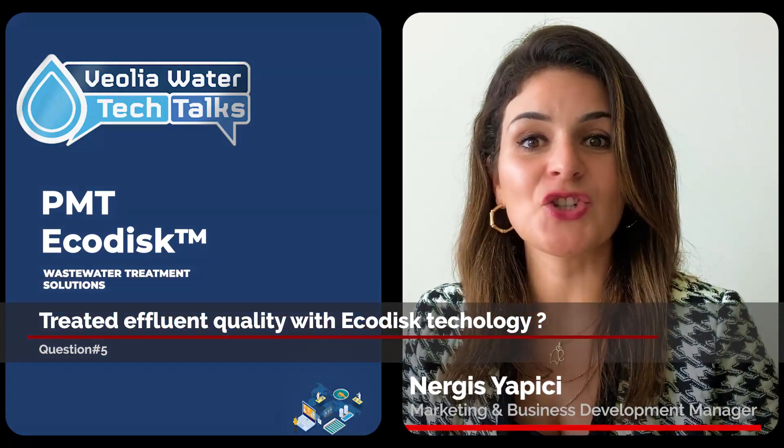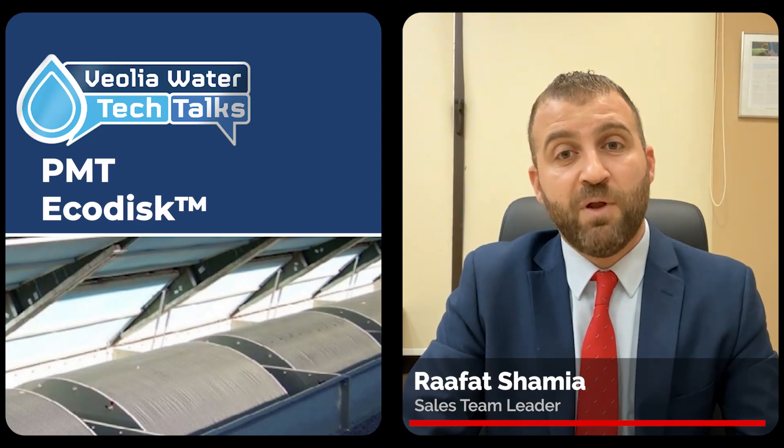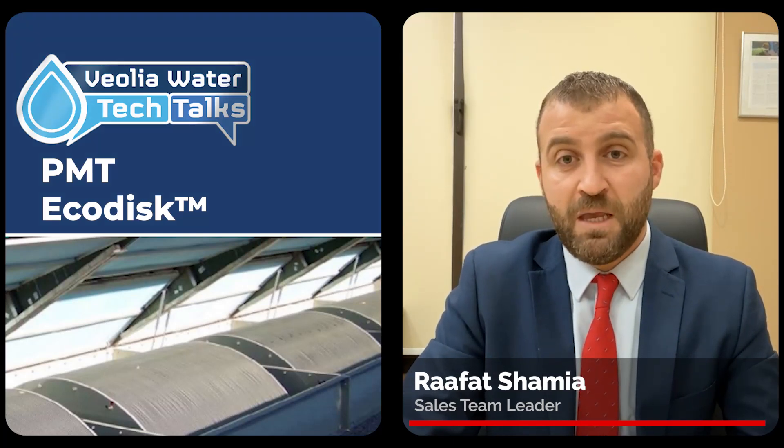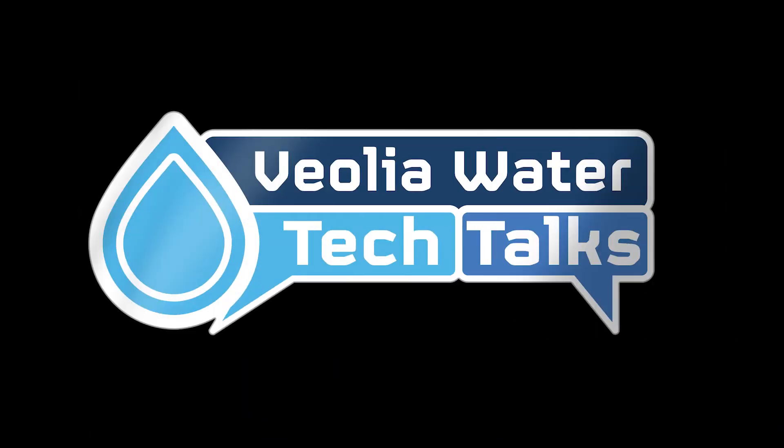Rifat, could you please share with us which treated effluent qualities we can ensure with Ecodisk technology? As of today, Ecodisk combined with lamella settlers maintains a standard of chemical oxygen demand (COD) of less than 120 ppm, biological oxygen demand (BOD) of less than 25 ppm, and total suspended solids (TSS) of less than 30 ppm. Since we are in an arid climate zone, this treated wastewater could be a great source for irrigation purposes, as Ali mentioned.